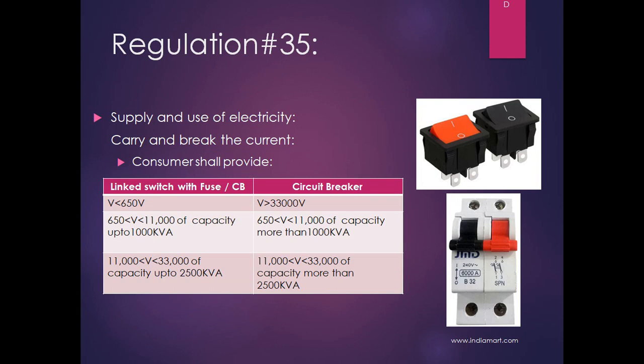Regulation 35 is regarding supply and use of electricity. This is regarding carry and break the current. The consumer shall provide, first we will see the left hand side, linked switch with fuse or circuit breaker for voltage level less than 650 volt. For voltage level less than 650 volt, linked switch or circuit breaker, linked switch with fuse or circuit breaker is sufficient. But if the voltage level is more than 33 kV, the consumer shall provide the circuit breaker only.